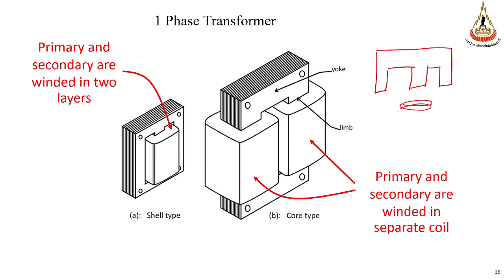And then we turn the coil into the bobbin, we call the bobbin. This is the, I will pass to you. It's a plastic mold, right? And then we put the primary and secondary to the same coil, right? With some insulation, and we put it into the core, right? And then we put the I area. So we call this type of transformer core as EI core. Yeah. So this is EI core, right?